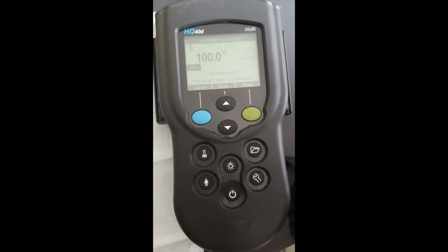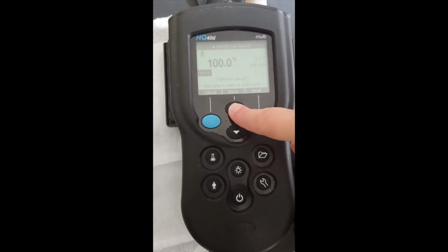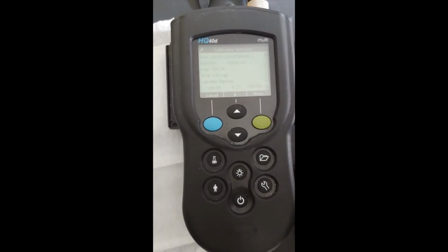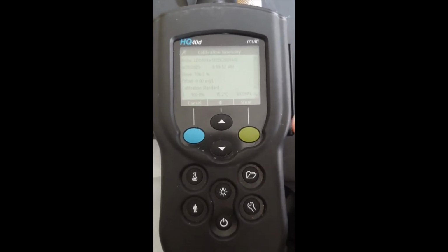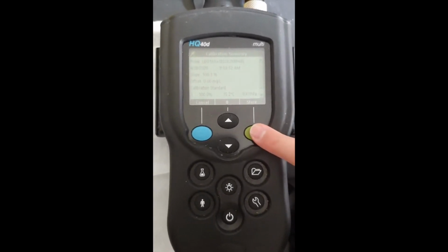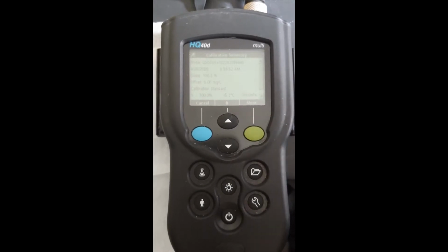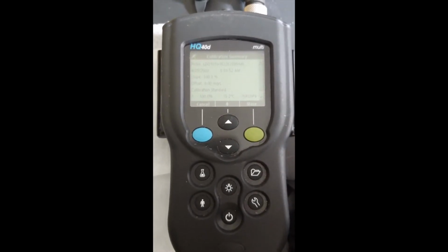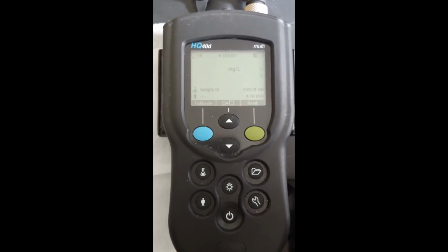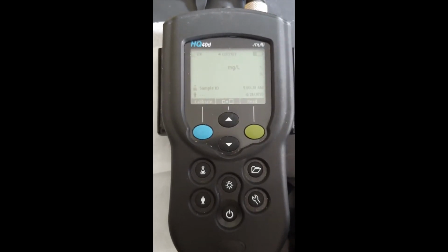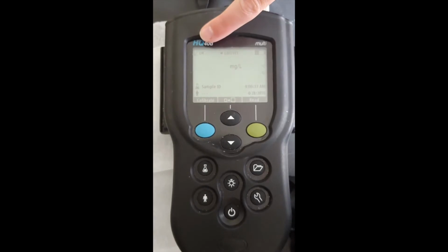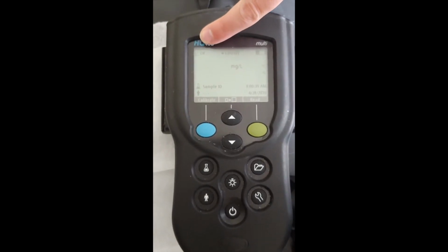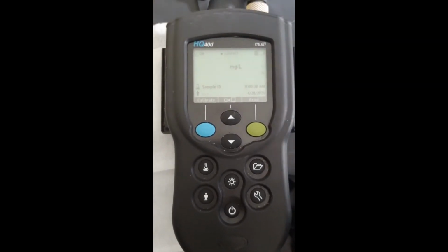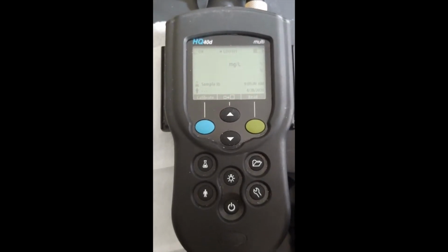Once you see the calibration hit 100%, you simply follow the prompts on the screen. So first we're going to hit the done button here, which then gives us the results of our calibration. And then most importantly, we want to hit the store button next. It may take a few seconds to register the next screen, so again, have some patience. Once your calibration has been done successfully, you should see an OK symbol in the upper left-hand portion of your screen. If you do not see this OK symbol, that means your calibration has not been stored correctly and you need to perform the calibration again.